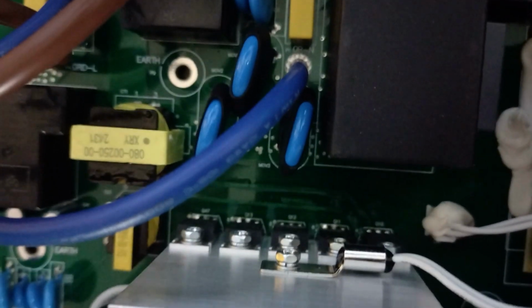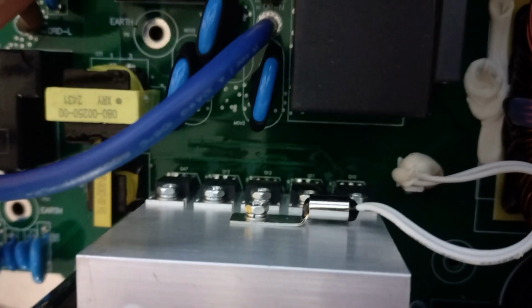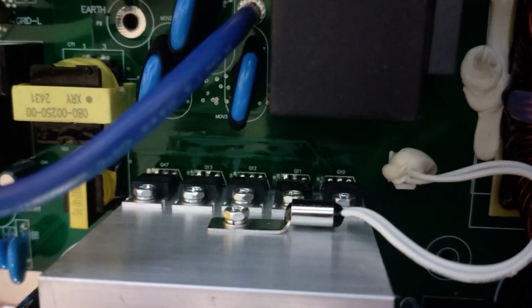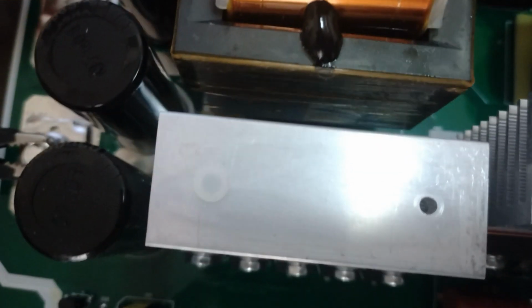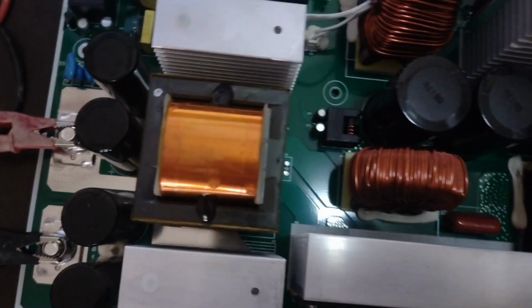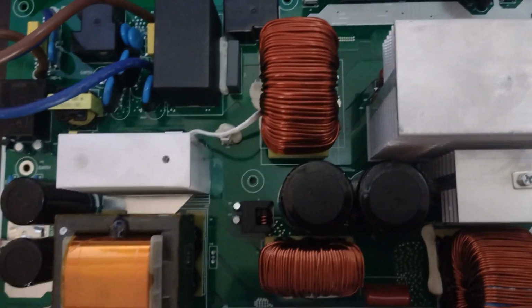I will have to double check all these MOSFETs. I'll get the infrared camera out and use that to make sure none of them are running hotter or cooler than the others. That's probably the best way to check, as they're all in parallel. But yep, I'll replace that IGBT and get back to you.